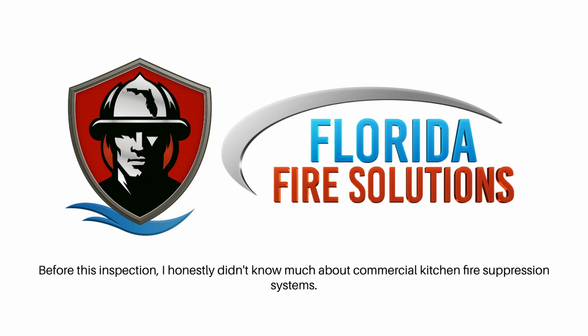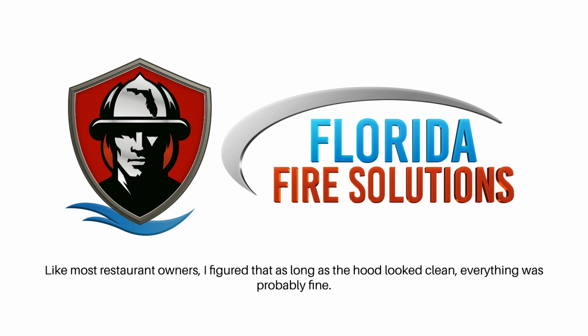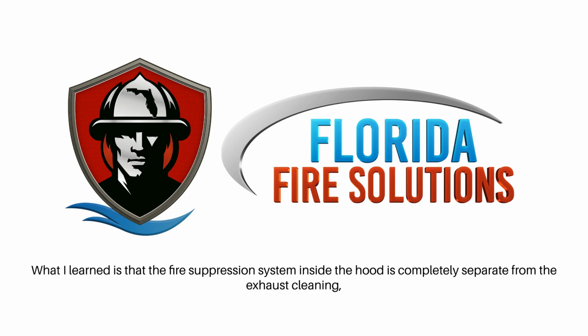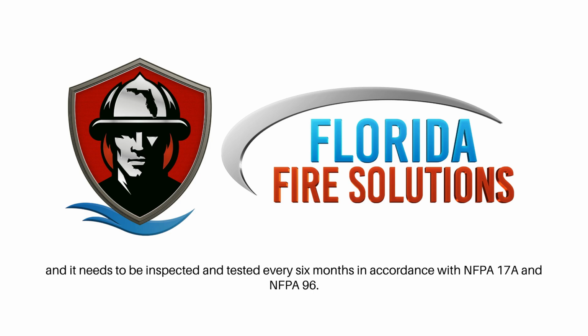Before this inspection, I honestly didn't know much about commercial kitchen fire suppression systems. Like most restaurant owners, I figured that as long as the hood looked clean, everything was probably fine. What I learned is that the fire suppression system inside the hood is completely separate from the exhaust cleaning, and it needs to be inspected and tested every 6 months in accordance with NFPA 17A and NFPA 96.